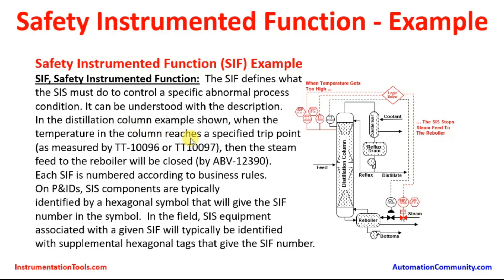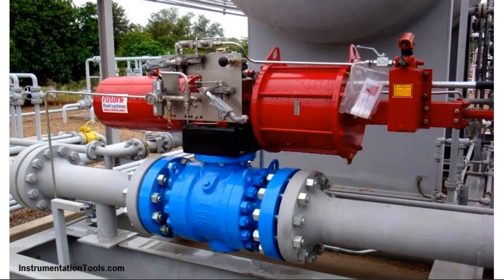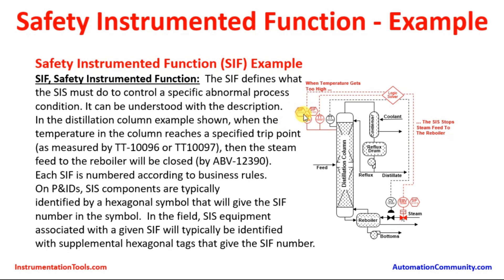In this distillation column example, when the temperature in the column reaches a specified setpoint as measured by TT10096 and TT10097, steam to the reboiler will be closed by ABV12390 — the automated block valve or emergency block valve. Each SIF is numbered according to the business rules. Here we see SIF 1111, so this particular safety instrumented function is numbered SIF 1111. All the sensors and the final control elements share the same SIF number.